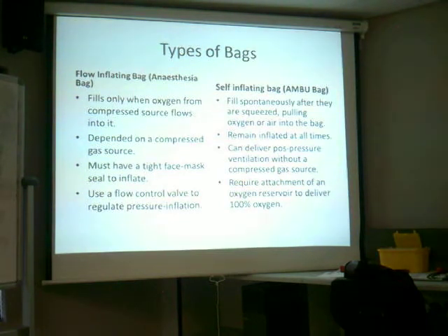Very nice question to ask in a table format: differentiate between a flow inflation bag and an ambu bag. It's dependent on compressed air. So if there's no compressed air, it doesn't work. You're going to sit there with a flat bag. You will not be able to resuscitate the patient. It must have a tight fitting mask. You will see that when you work in theatre, the mask looks a little bit different than the ambu bag mask. So this one is dependent on the fact that it fits tight around the patient's mouth.